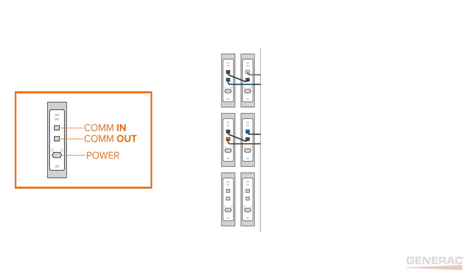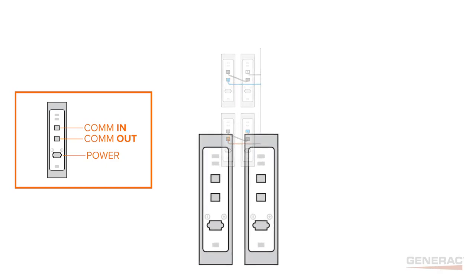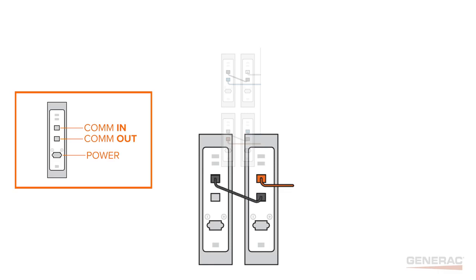On the bottom shelf, connect the orange Ethernet-style cable to the rear battery's COM-IN port, but leave the front battery's COM-OUT port open. Note that regardless of how many battery modules are part of your installation, nothing needs to be connected to the COM-OUT port of the last module. Then, take the last Ethernet jumper cable and install it between the back battery's COM-OUT port and the front battery's COM-IN port.